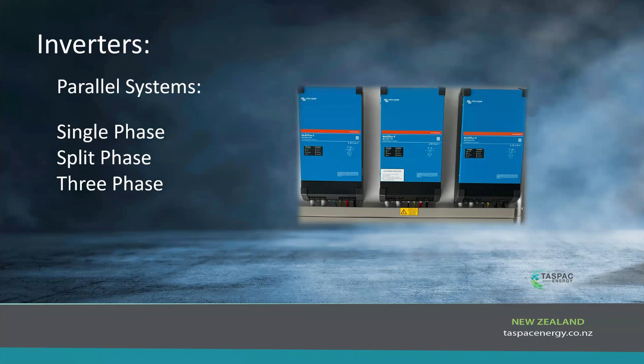The rule is the inverters have to be identical, so they have to have the same firmware in them. They have to have the same chipset in them. So you can't buy, say, a Multiplus 2 that was built 5 years ago, which they didn't exist then, and then try and buy a brand new one and parallel those two up. There's a risk that the chipset won't be the same and they won't work together. And there are some other rules about multi-phase systems that you need to study and know. It starts getting reasonably complex when you set a multi-phase system up, so it's not the same as a single phase setup. Just ask. I can certainly help you through what you need to know there.